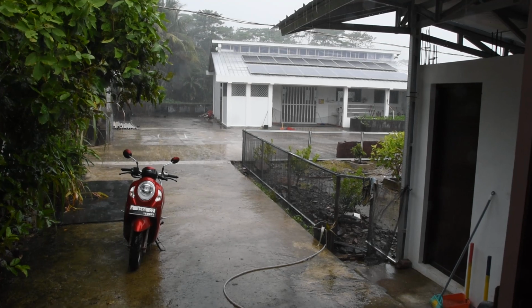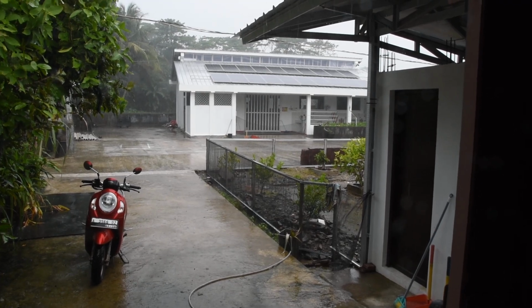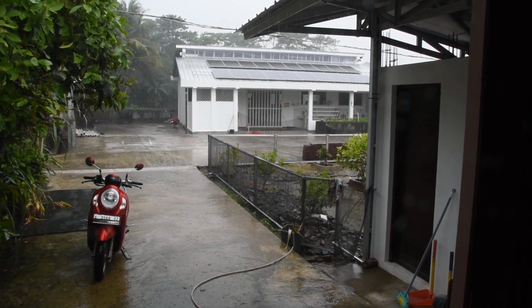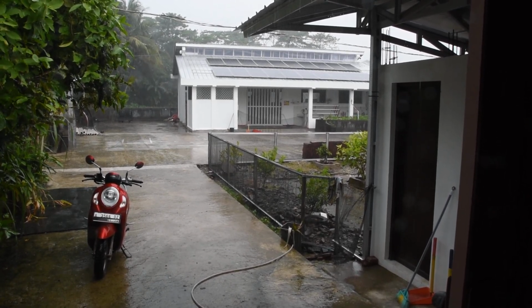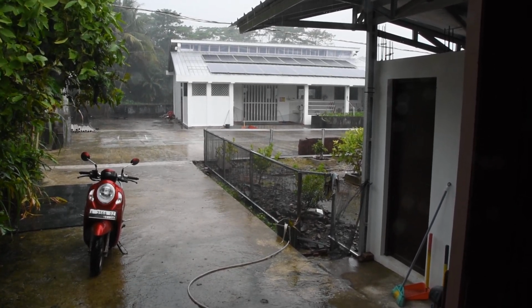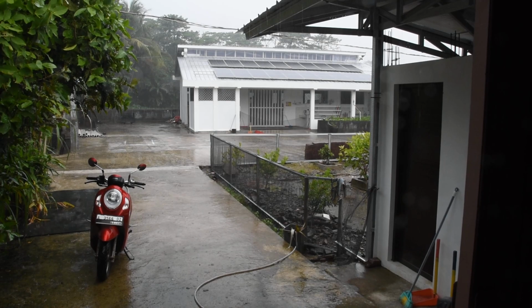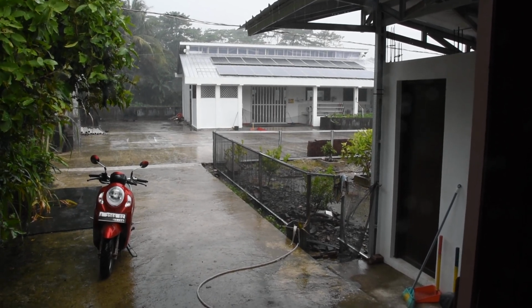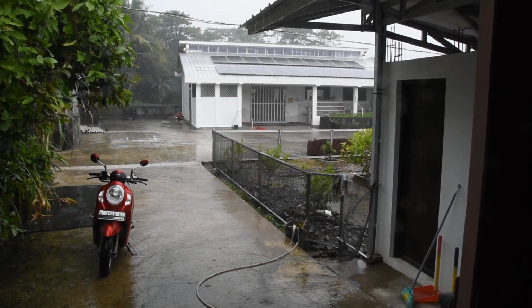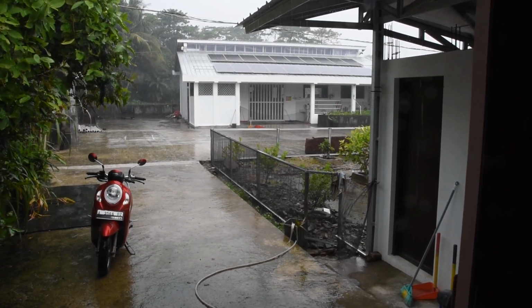What I'd like to do is get some changes to the settings for charging of the shed from the genset, because at the moment there's just one generic blank setting where it says if you fall below 25%, charge to 40% or run for at least half an hour. And normally, under no load at the shed, that will get you up to about 44%. Often the house will be drawing charge at the same time, so it takes longer to get up to 40%, or it doesn't get as high as 44%.